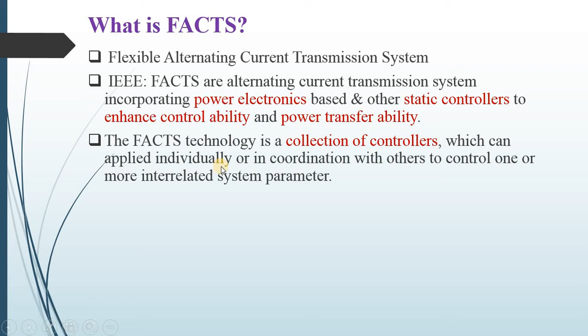Also, it can be defined as: FACTS technology is a collection of controllers which can be applied individually or in coordination with others to control one or more interrelated system parameters. The different controlling parameters are series impedance, shunt impedance, current, voltage, damping of oscillations, and power angle. So with the help of FACTS technology, we can control these parameters individually or one or more parameters in the same device. This is the general symbol of a FACTS controller that can be used while representing it in a circuit diagram.